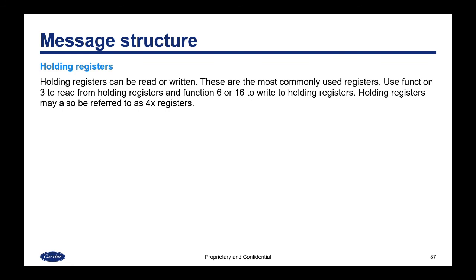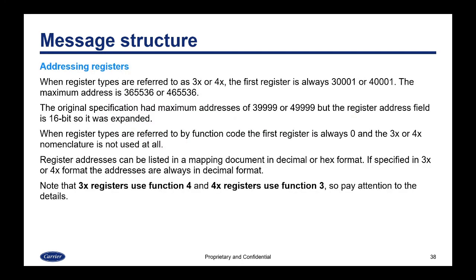Holding registers can be read or written — these are the most commonly used registers. You would use Function 3 to read from holding registers, and Function 6 or 16 to write to them. Holding registers may also be referred to as 4x registers. When register types are referred to as 3x or 4x, the first register is always 30001 or 40001, and the maximum address allowed is 365536 or 465536. The original specification had maximum addresses of 39999 or 49999, but the register address field is 16-bit, so it was expanded because there was no reason to limit it to 10,000 addresses.